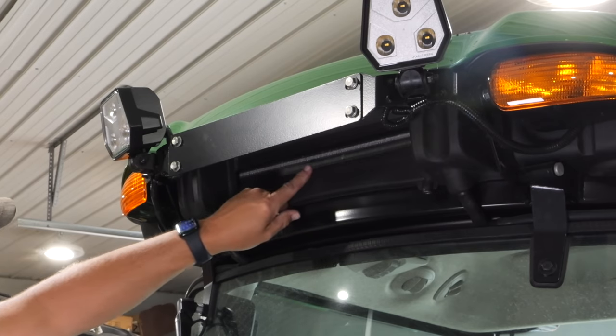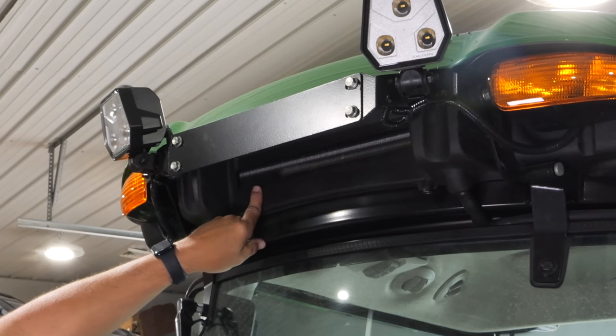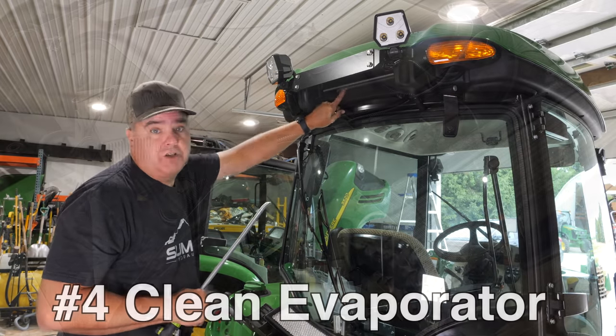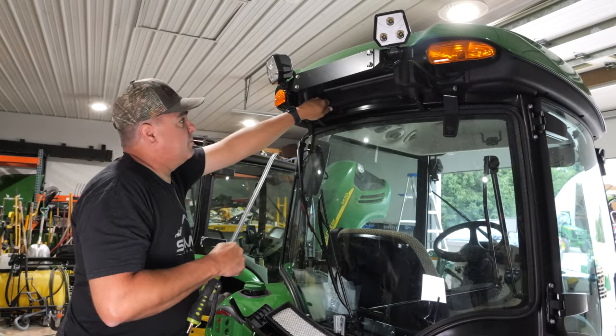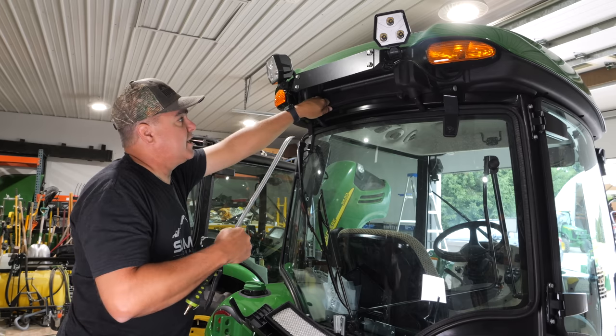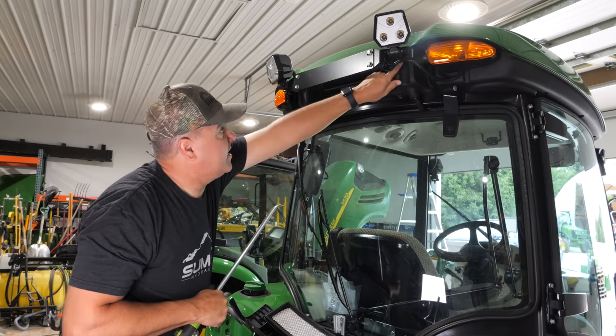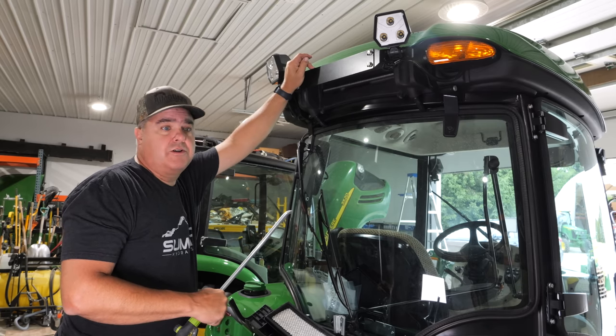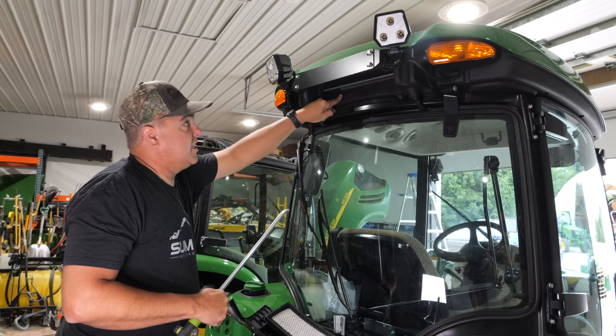While you've got the filter off, you get a little bit of a view of the evaporator up here — unfortunately not enough view. The next item on our list is making sure that this evaporator is clean. Even with decent filter maintenance, this will become plugged. When I got my 3520, it was absolutely solid plugged all along the backside, even on top. It had 3,600 hours on it and I suspect it had never really been cleaned. To do that, I'd recommend taking the roof off — it isn't that hard. There are 13 bolts, and they're just 13-millimeter bolts.